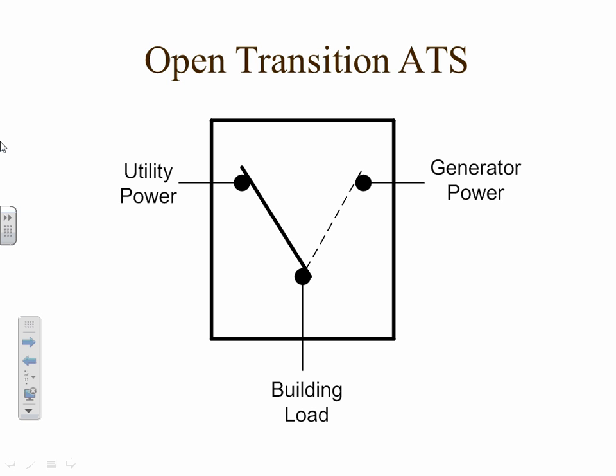So that's the final time delay, is time delay stop. So time delay start, make sure it's a real outage. Time delay transfer, if we can, with a non-emergency or non-legally required transfer switch, give the engine a little time to stabilize before we hit it with a load. Time delay on retransfer to make sure the utility is really there for good for the duration. And time delay stop, so that engine has cooled its turbocharger down. All the transfer switches we'll be going through have those same 4 time delays in there. And some of them got a little more sophisticated and put more in for other things, but those are the basic 4 that you'll always see.